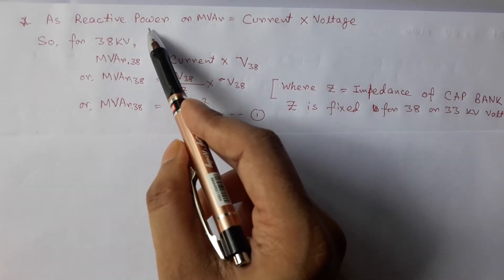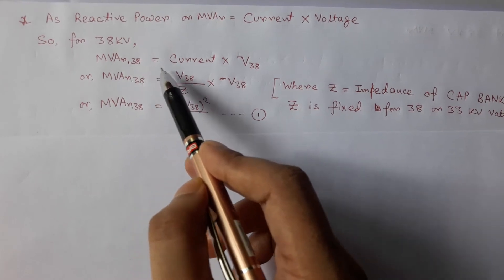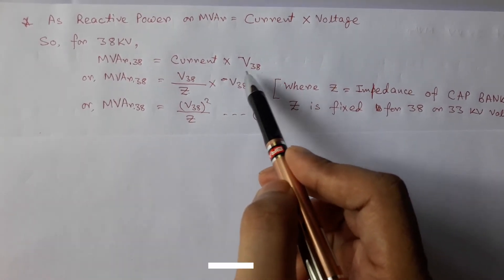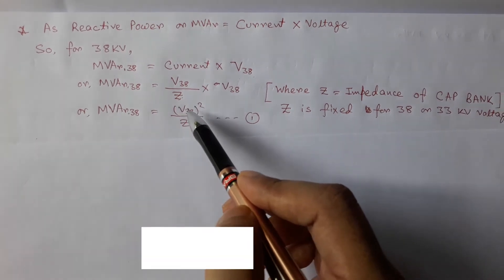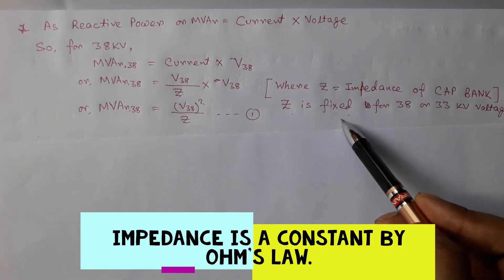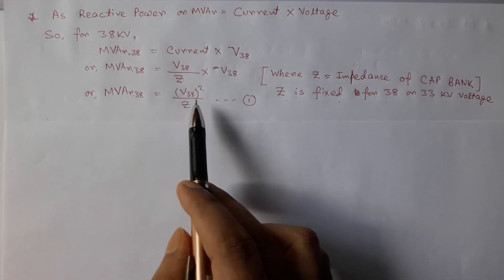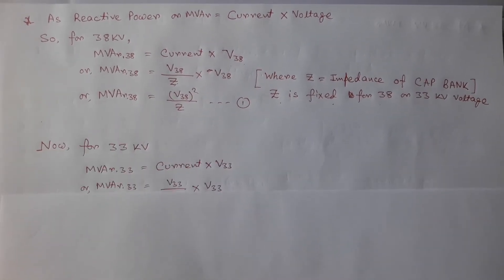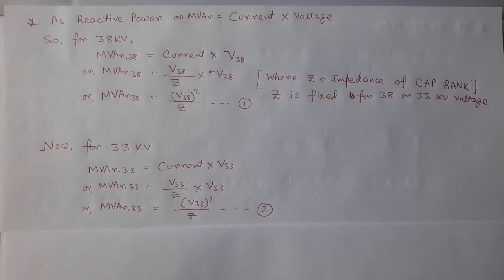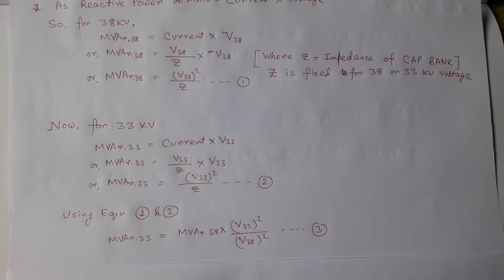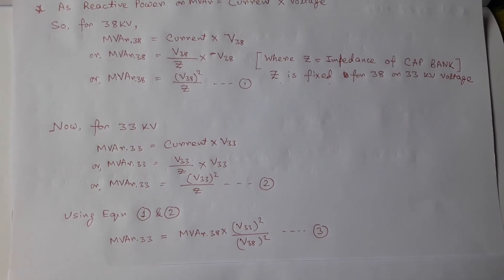We know that reactive power is the multiplication of current and voltage. For 38 kV, we replace the current term with voltage divided by impedance. The impedance of a capacitor bank is fixed — it does not change with system voltage. So for 38 kV we can write equation 1, and since our capacitor bank will be connected at 33 kV, we write equation 2. Using equations 1 and 2 together gives us equation 3 to find the mVar rating at 33 kV from the 38 kV nameplate data.